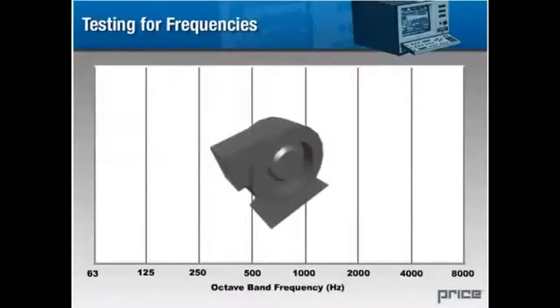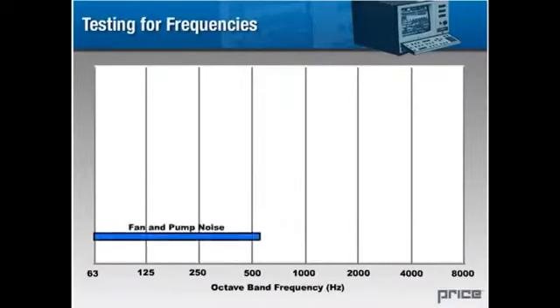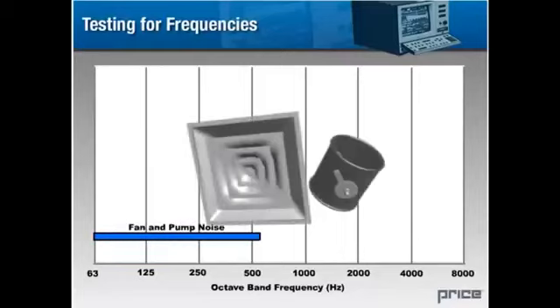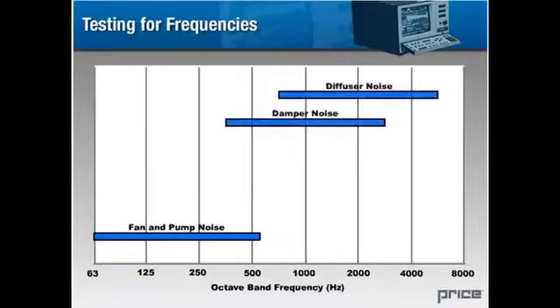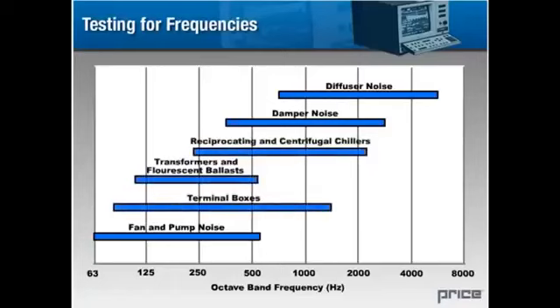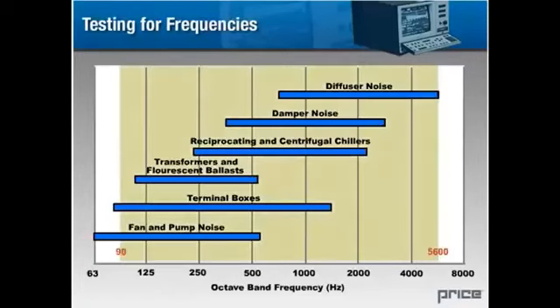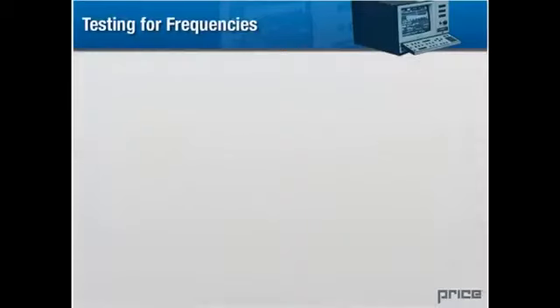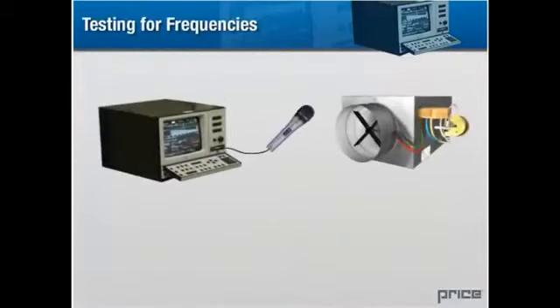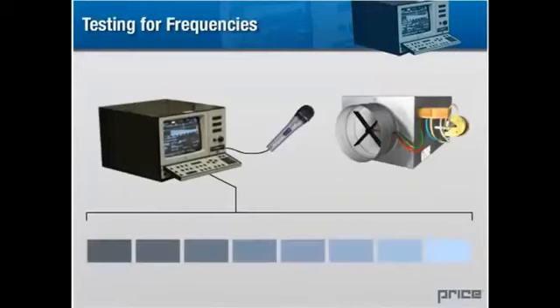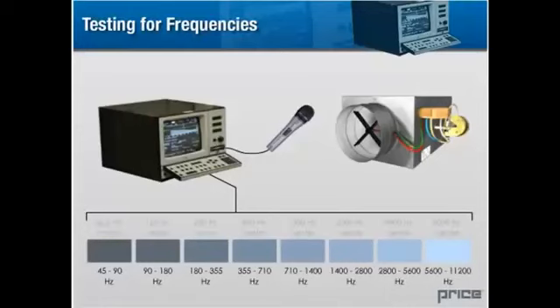For instance, a fan might produce a lot of low-frequency noise due to its motor. High-frequency noise might be produced by airflow through dampers or diffusers. The normal range of concern for most air terminal devices is in the 90 to 5600 Hz range. To derive frequency-specific test data, electronic filters are used to isolate noise occurring in the following frequency ranges. Note that each of the frequency bands is centered on a frequency which is double that of its predecessor.